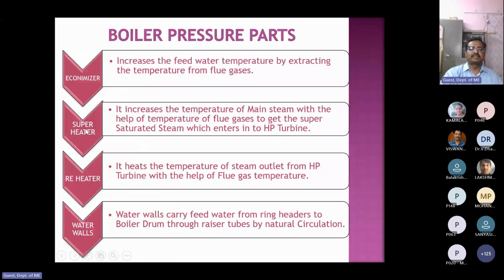For example, the superheater is arranged after the boiler drum. The saturated steam coming from the drum goes to the superheater, and its temperature is raised at constant pressure. That superheated steam is then supplied to the turbine, where it expands partially. After some intermediate pressure, the steam comes back to the boiler, which is called the reheater. It is a modern Rankine cycle plant, that is, we are utilizing superheater, reheater and regeneration also. In the reheater, at lower pressure, its temperature increases again and it goes to the next turbine, called the intermediate pressure turbine or low pressure turbine.